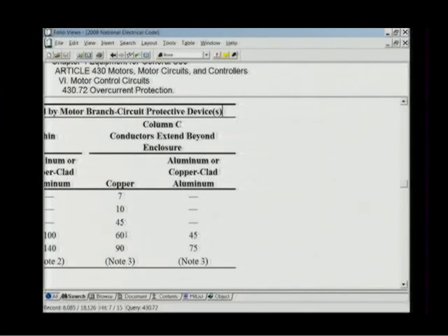Okay. All right. Let me see if I can give a summary here because this is like, what's going on? I like to distill this down to what do I need to know as an electrician? Just cut it all off. Here's the deal. If you have a motor circuit and the motor branch circuit short circuit protection device, going to Table 430.72, isn't beyond 60 amps, then you could make a tap off of the motor branch circuit conductors and you could use 12 gauge wire.